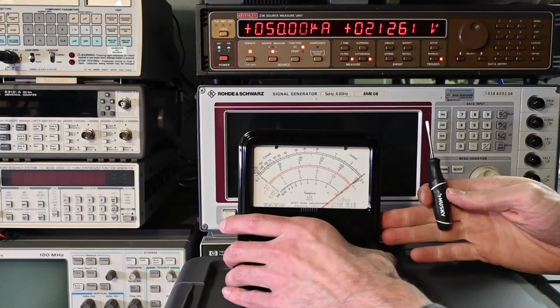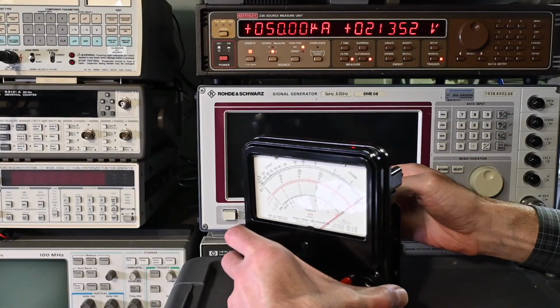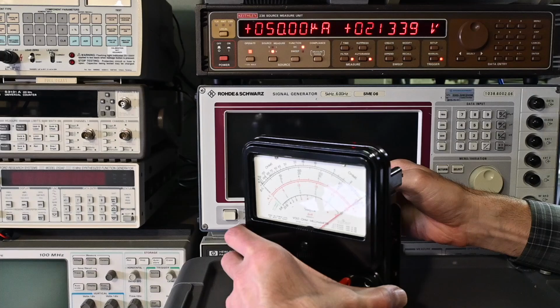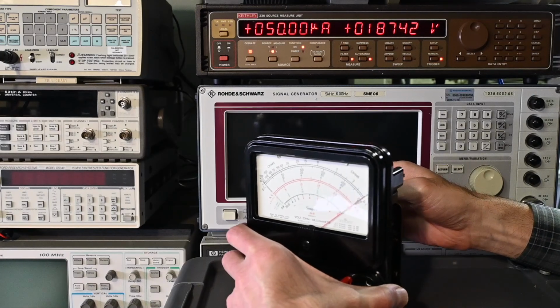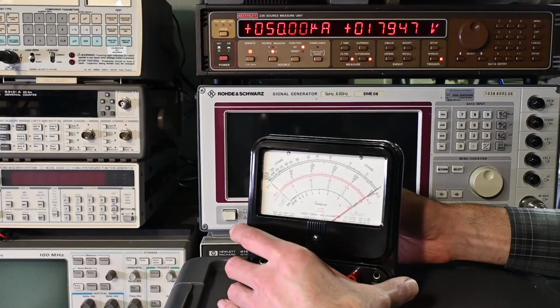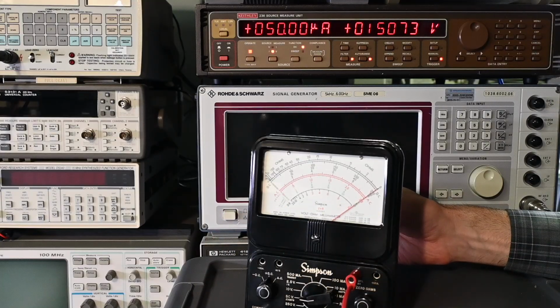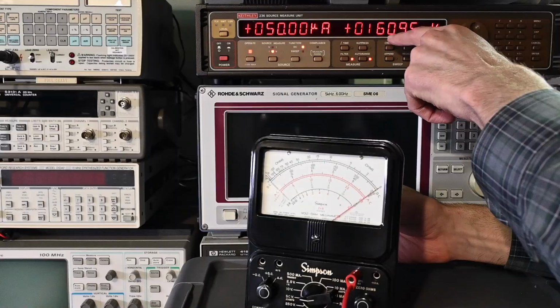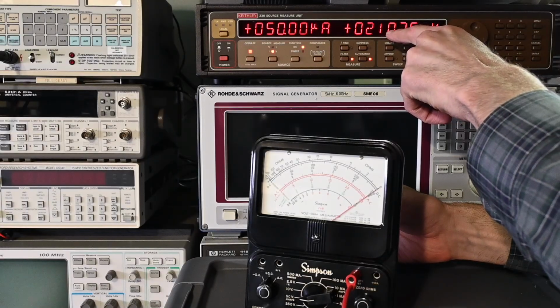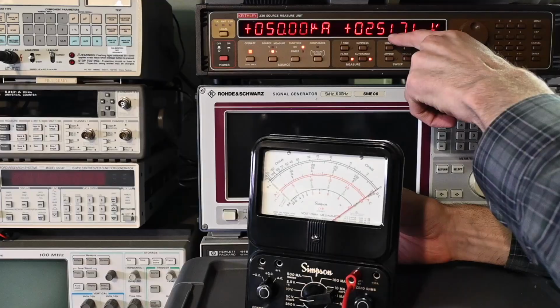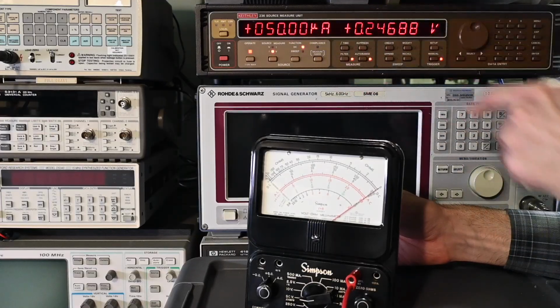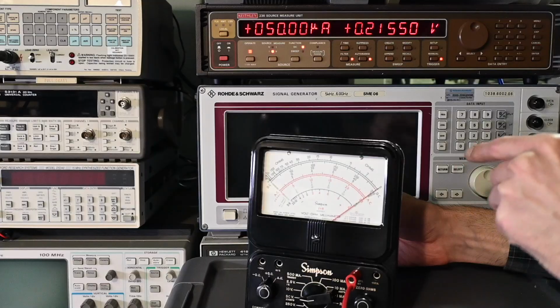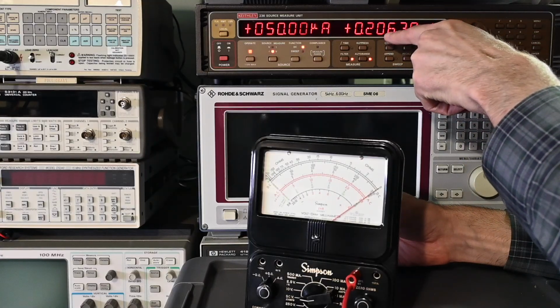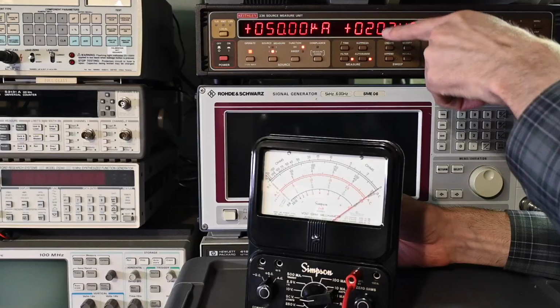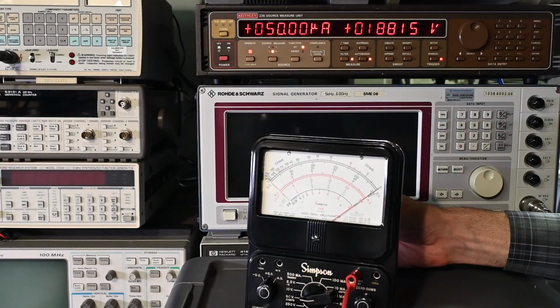So I'm going to turn this adjustment here, the second DC calibration potentiometer right here, and get this screwdriver to go in there. Okay, there it goes. So I'm going to start making the adjustment, and notice the voltage, how it's changing. And I'll go the other direction here. Notice how it's increasing. So the voltage is changing, but of course we're in constant current mode, so this doesn't change. As I'm rotating that potentiometer, we just see that the source voltage is changing to ensure that 50 microamps continues to flow, even though the circuit resistance is essentially changing.